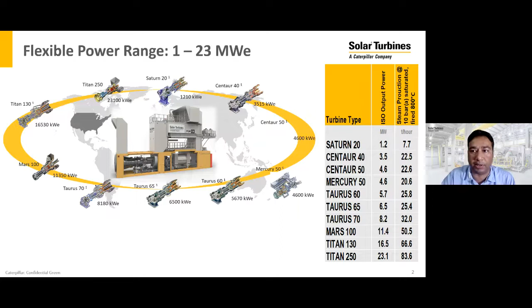The steam can be generated from the gas turbine exhaust. It can be unfired, so we can completely utilize the exhaust of the gas turbine to generate the steam or chilling, or in case the requirement is higher, we can do supplementary firing in the HRSG up to 800 degrees centigrade or higher, depending on the requirement. The steam can be generated with the 1.2 megawatt gas turbine Saturn 20. We can generate something like 7 to 8 TPH of steam. So that's entirely depending on the customer's requirement. We can design the plant.